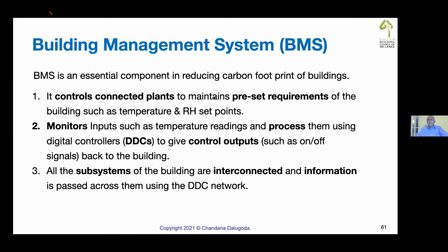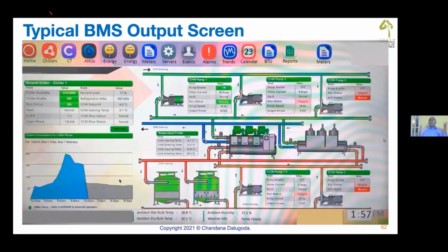Then obviously you must have a building management system. I'm not going to go into details. Without a building management system, we can't see that you are having a successful green building, because there are so many energy saving strategies you can do with the BMS, like chilled water reset, fan cycling, demand limiting, night purge, so many things. So you need a true BMS, not a BMS where you look at the pictures and the moving things. No, actual power saving.